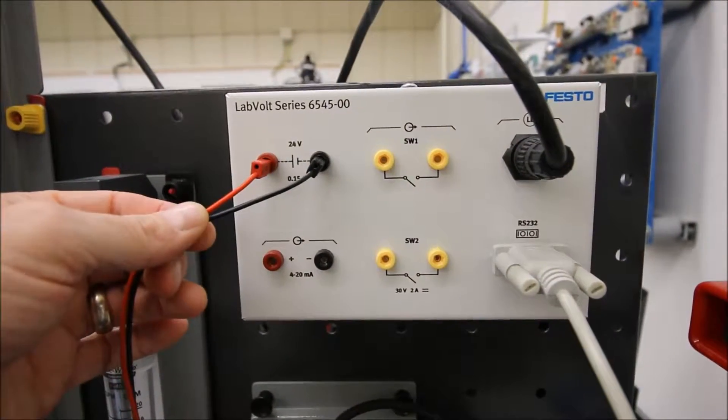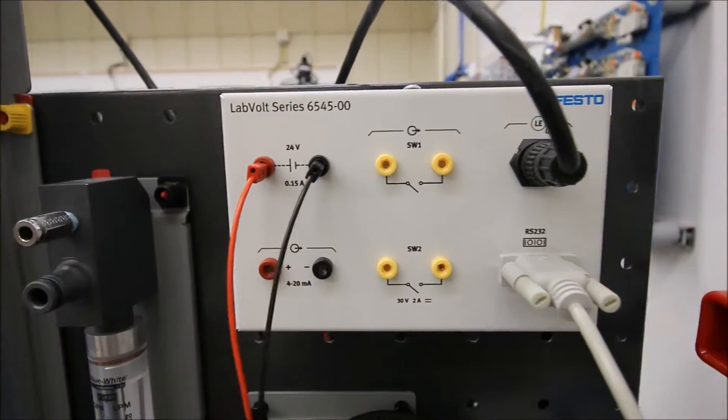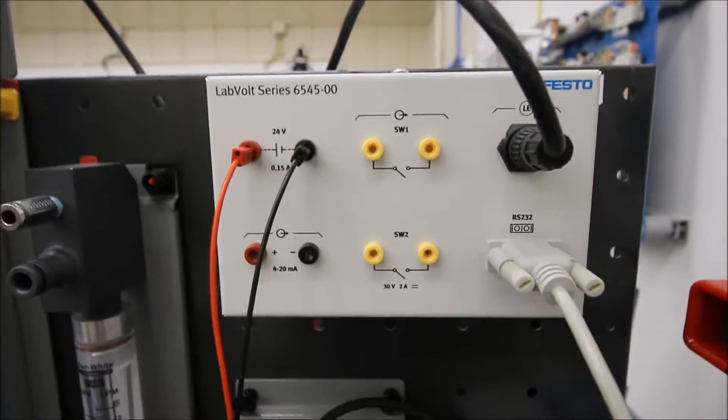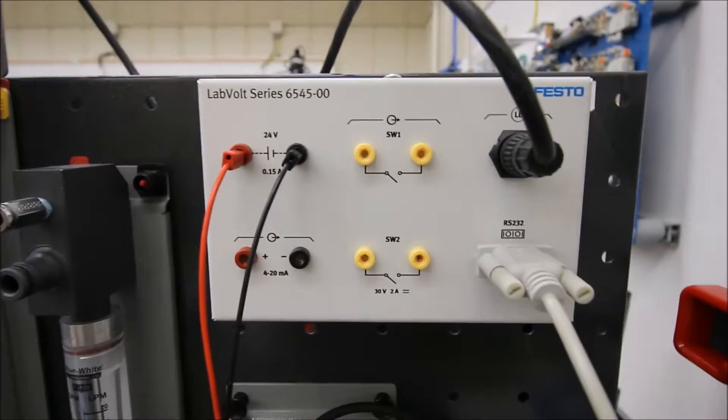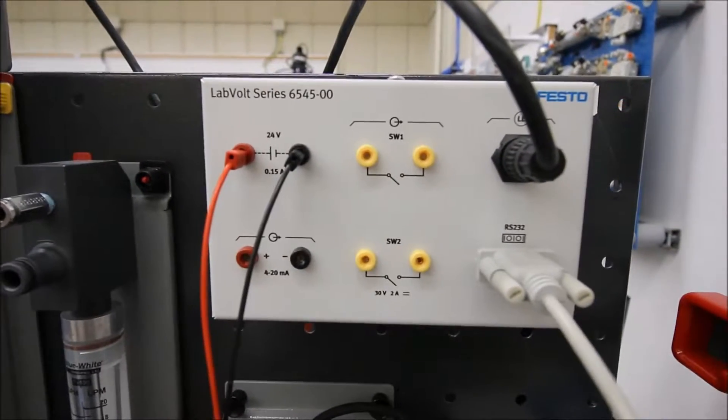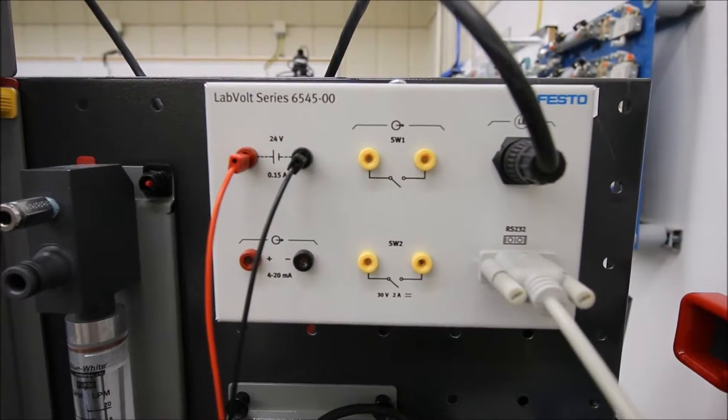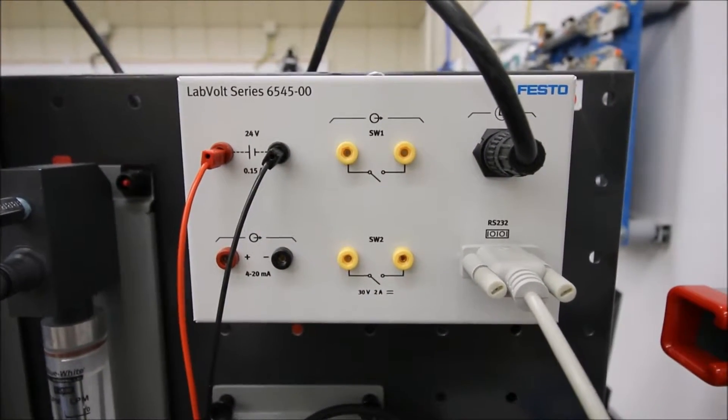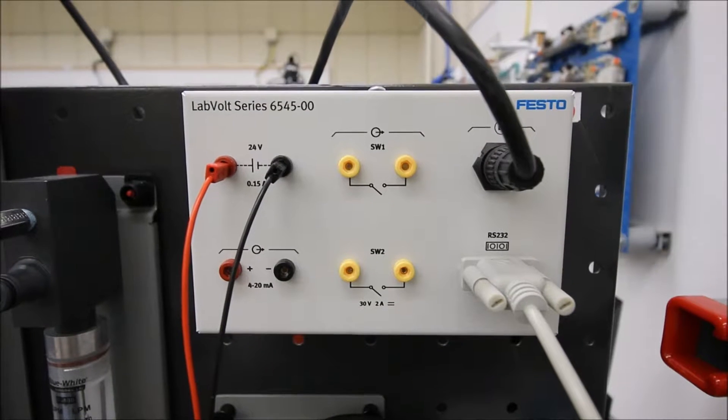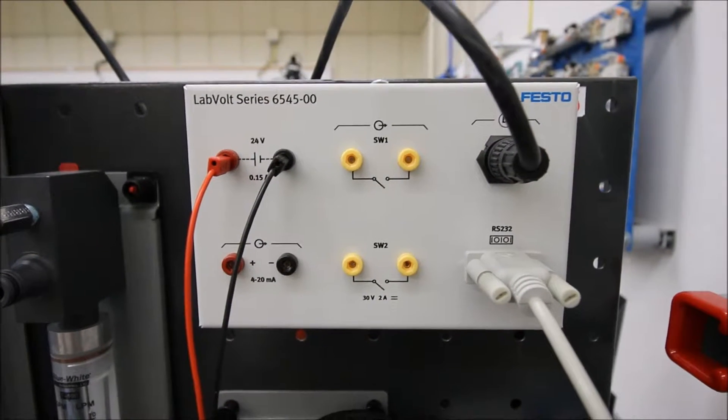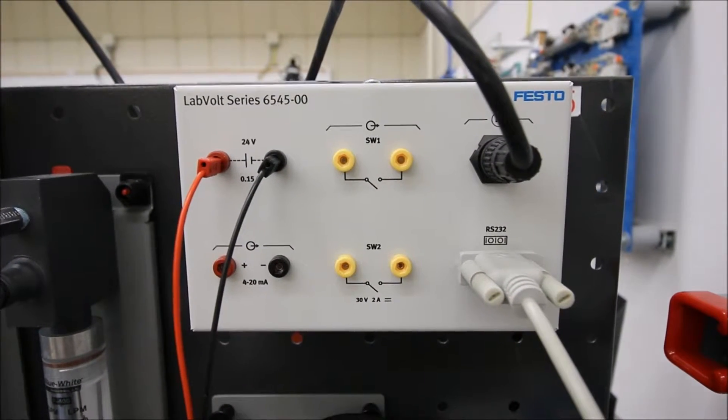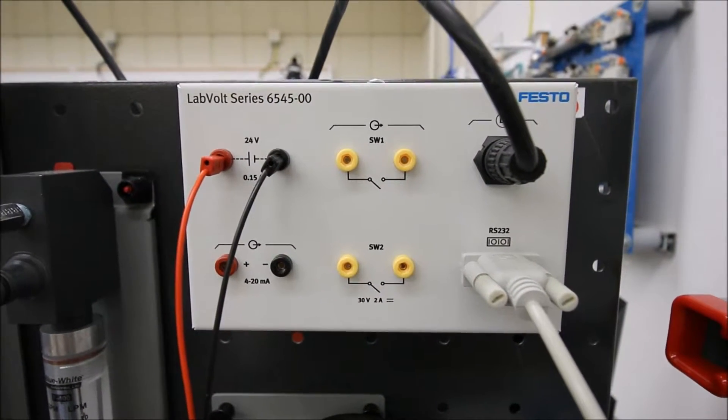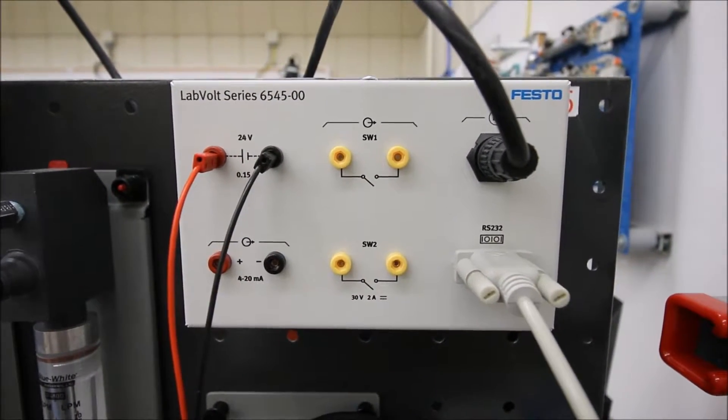We have an RS-232 link over to the computer. Right now we're at the highest level of the tank at 50 centimeters, that should correspond to a 20 milliamp signal. Let's take a look at the computer and see what we have on display.